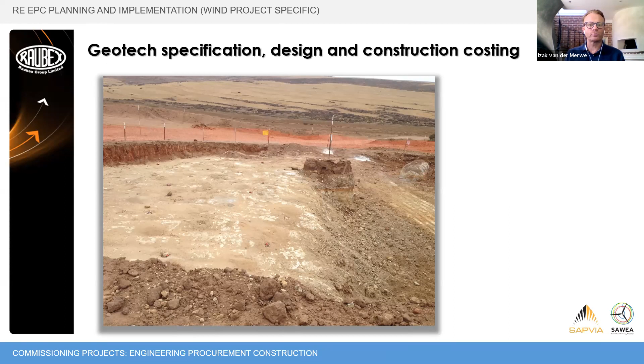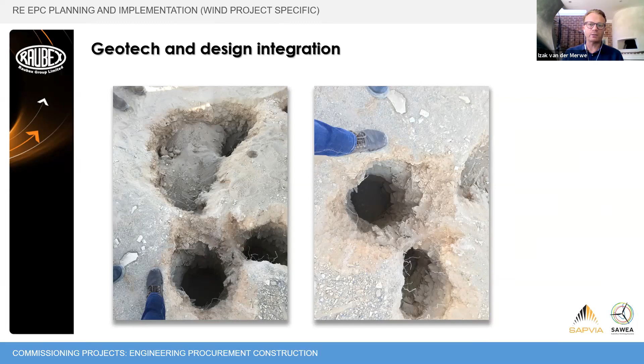This is where the geotech becomes a process, and where there's a serious disconnect between the geotech and the design. As you can see in these soil conditions—I'm an electrical guy, not a geotech expert, but I can see quite easily in the photo this is shale, and you cannot install a piled foundation in this case simply because the shale just caves in. Some of these holes are supposed to be a 300 millimeter diameter hole, but it starts off at 500 at the top, and further down it becomes much wider even. So this is a good example of where the design should have been changed after the geotech investigation.